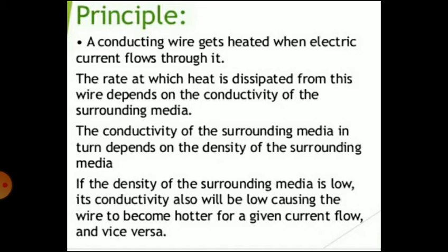If the pressure changes, and the wire is resistively heated by current from a constant power source, a new thermal equilibrium will be reached. The temperature of the wire will change to reflect the new number of gas molecules that can carry heat away from the wire. So the temperature of the wire can be used as an indication of the pressure within the envelope.